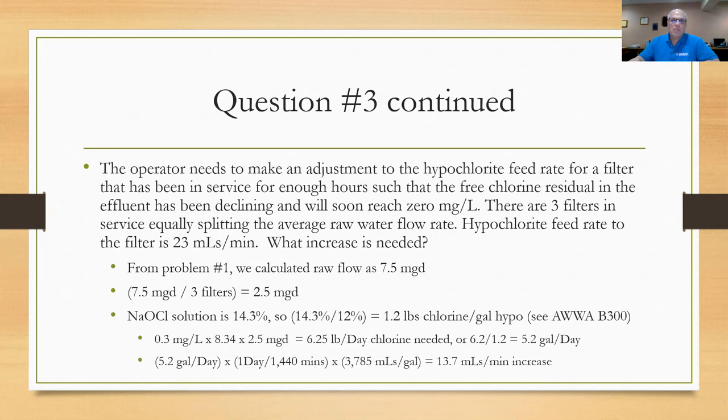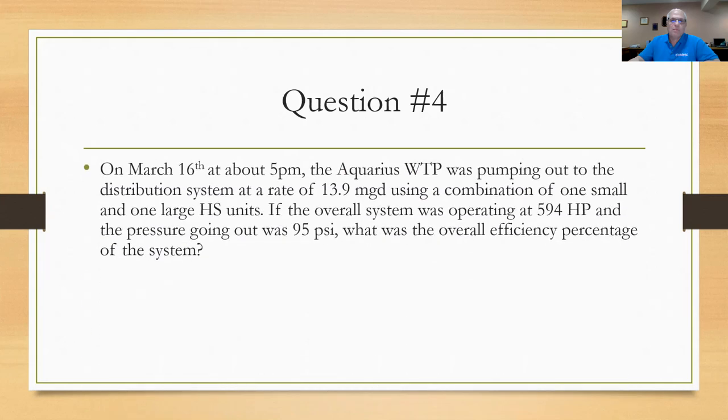Let's try question number four. When I look through the data, I see that on March 16th at about 5 p.m., the Aquarius water plant was pumping out to the distribution system at a rate of 13.9 mgd. Remember, the average was about 7.5 mgd, but on this particular hour they were at a rate of 13.9 mgd. We're using a small pump and a large pump. If the overall system operating at 594 horsepower, the pressure going out the door was 95 psi, what's the overall efficiency percentage of the system? So you've got to take the horsepower formula, recalculate it for efficiency percentage by plugging in some of these numbers.